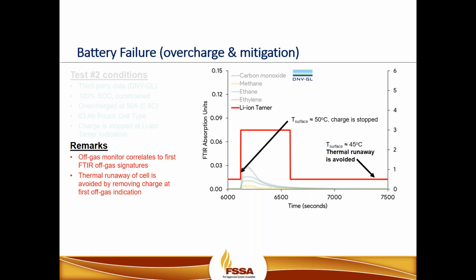So here you see the overcharging event occurring, and of course it happens at relatively low temperature, roughly about 45 degrees Celsius or 113 degrees Fahrenheit. All the data that is available on the market today shows that there are not very many thermal runaway events or fires associated with batteries operating in this temperature range. So while we have an overcharging event occurring, there is no increase in temperature. So the battery management system, while it's doing all its other tasks, may be challenged to provide indication that an abuse factor is occurring. So this is where an off-gas monitor provides critical time and information to be able to address the situation.